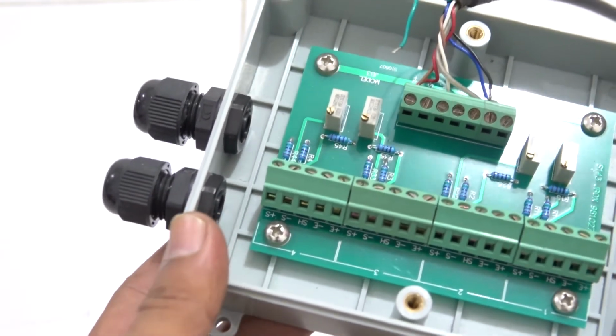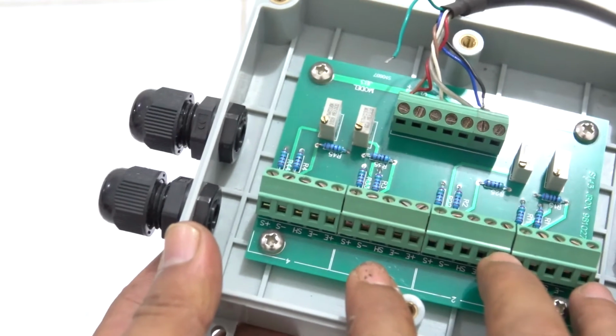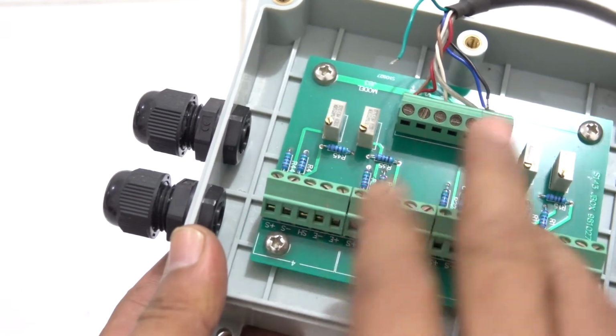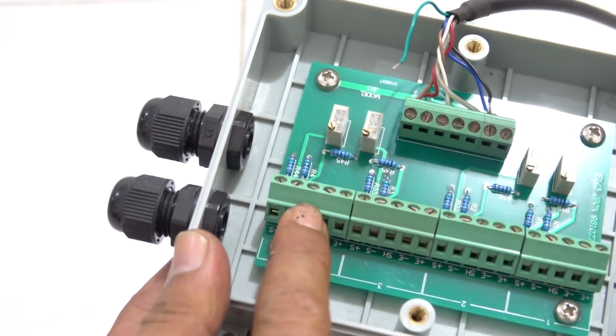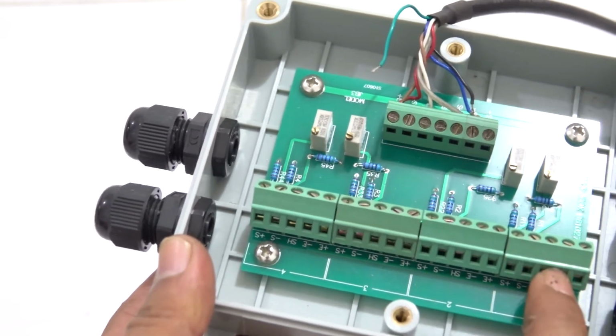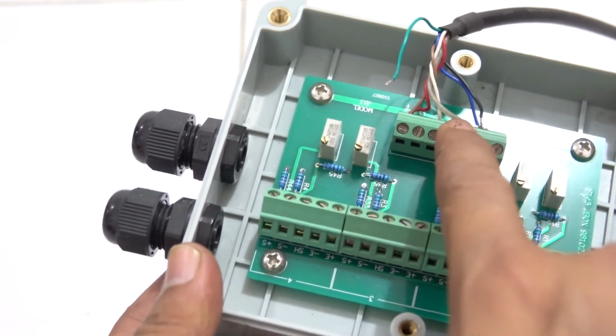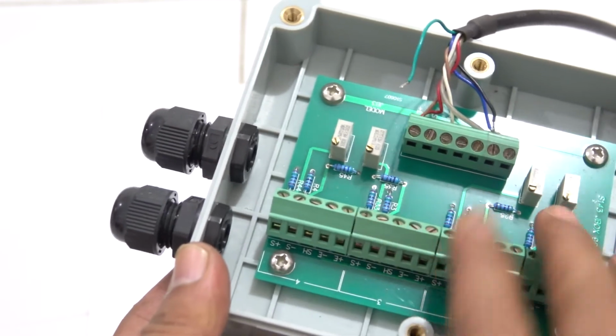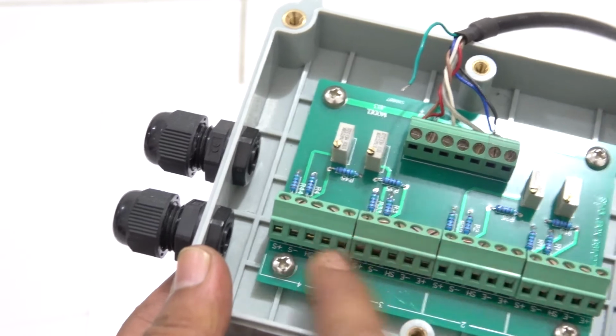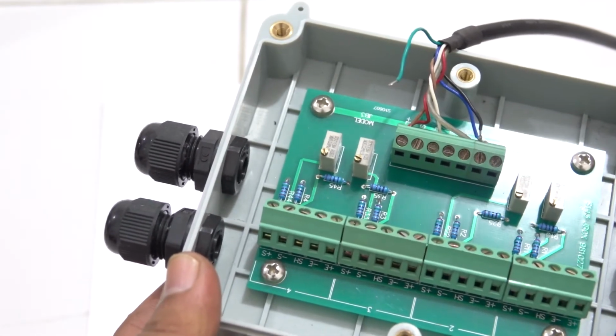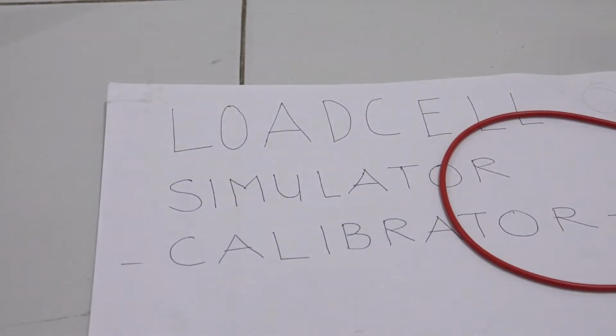Bear in mind that the junction box or summing box will not sum all the voltage. Let's say, for example, this load cell generates 4 millivolts, this 4 millivolts, 4 millivolts. It doesn't mean that this will generate 12 millivolts. No, they will find some smaller one, and you can adjust. They call it cornering. You can adjust, and this will go to the load cell indicator. The price of this is about 200 US dollars. This also is around 250 US dollars.